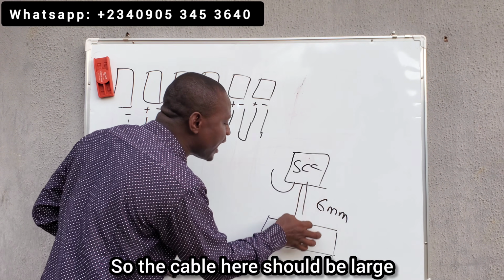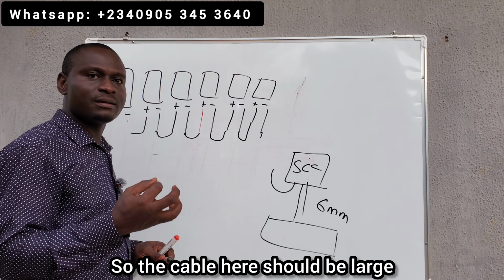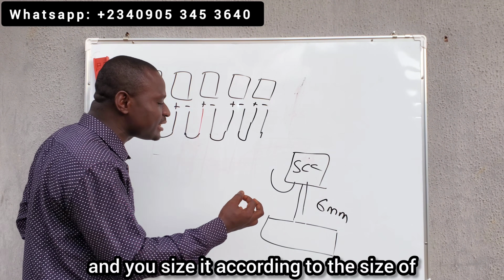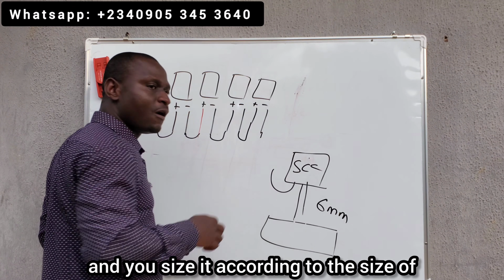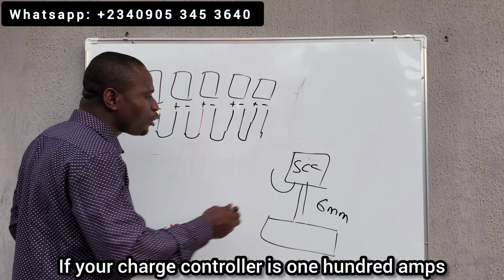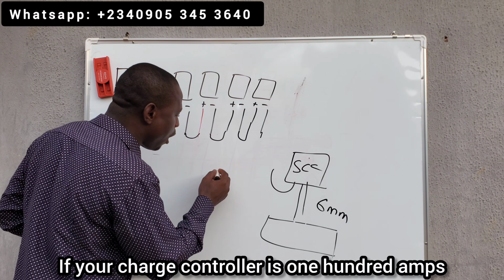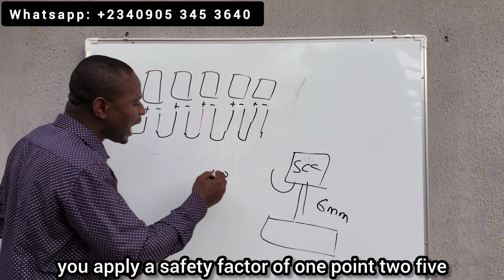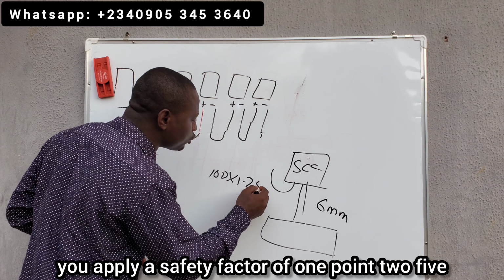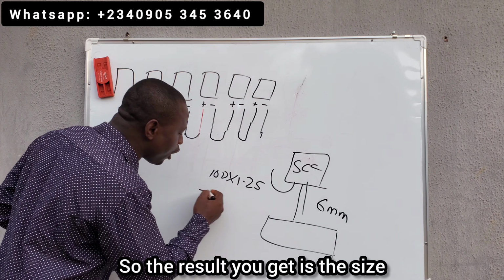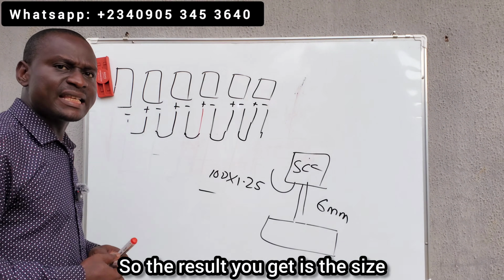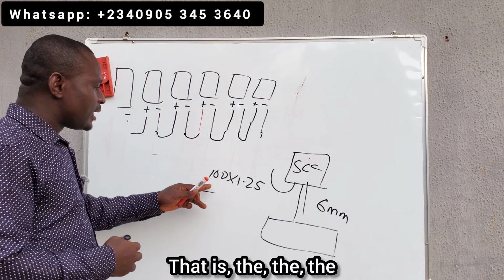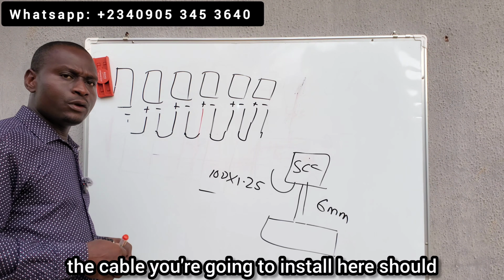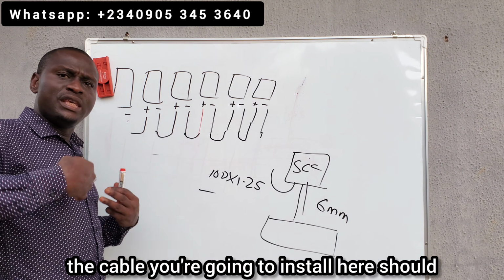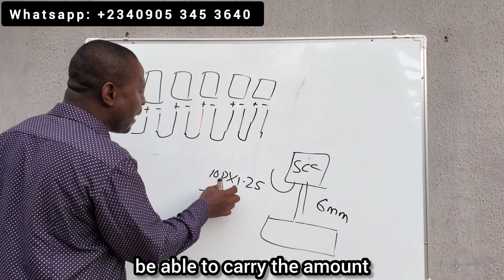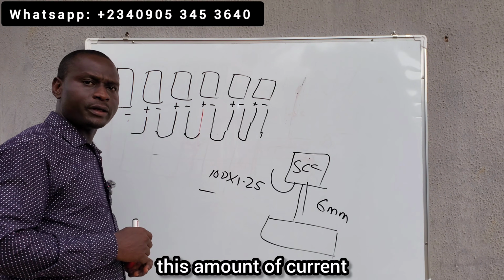So the cable here should be large, and you will size it according to the size of the charge controller. If your charge controller is 100 amps, you apply a safety factor of 1.25. The result you get is the size — the cable you install here should be able to carry this amount of current.